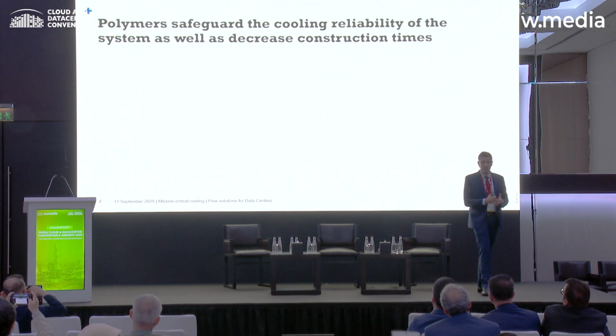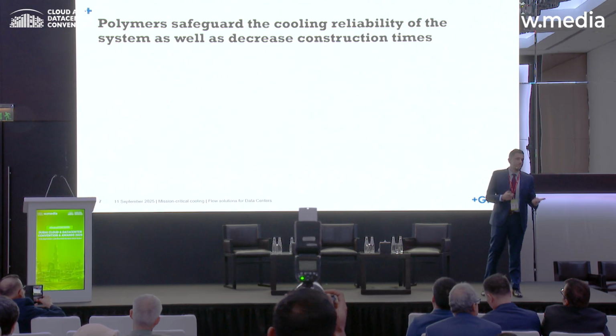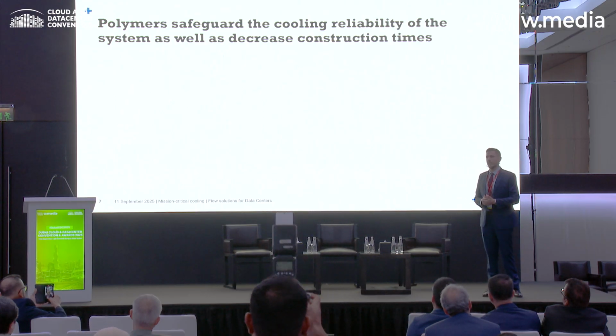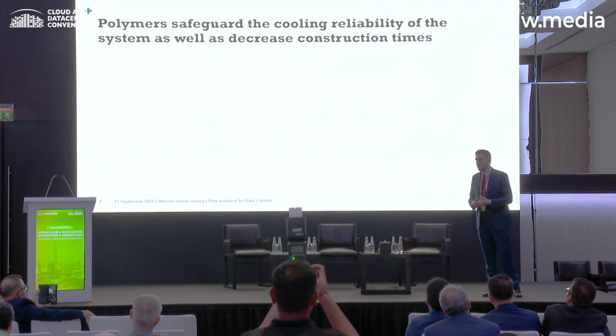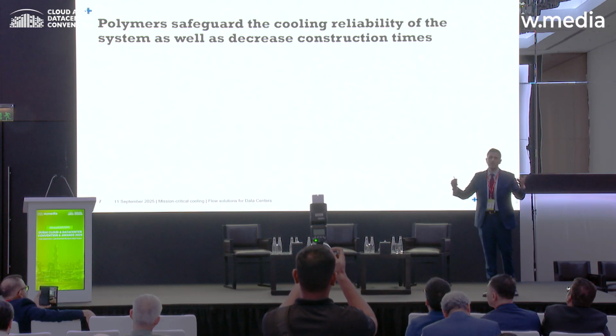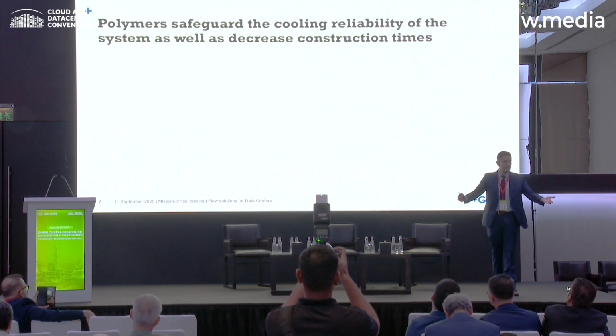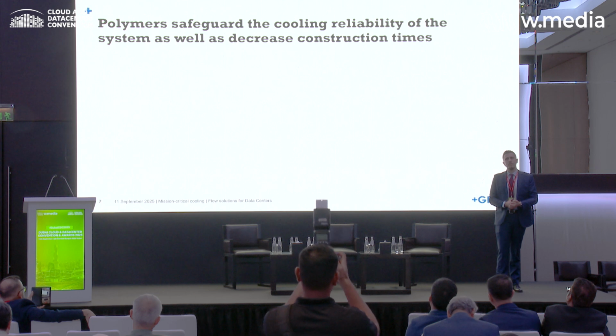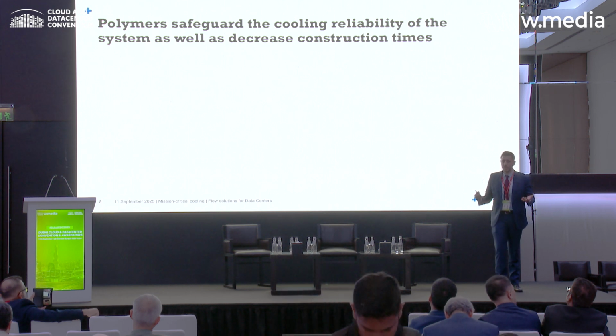Starting with the chilled water system, the polymer found to be the best fit for such application is high-density polyethylene, for different reasons. First, its ability to meet pressure and temperature requirements. It's found in different pressure ratings—10 bar, 16 bar, 20 bar—way more than the industry or application needs. In terms of temperature resistance, it's up to 60 degrees.